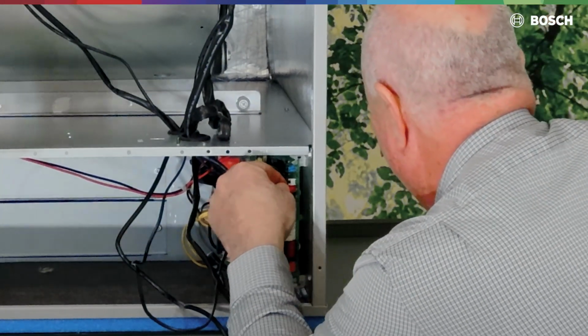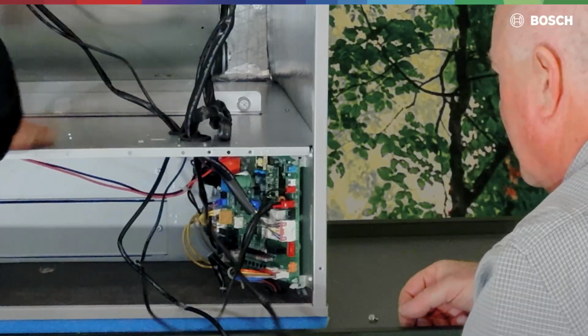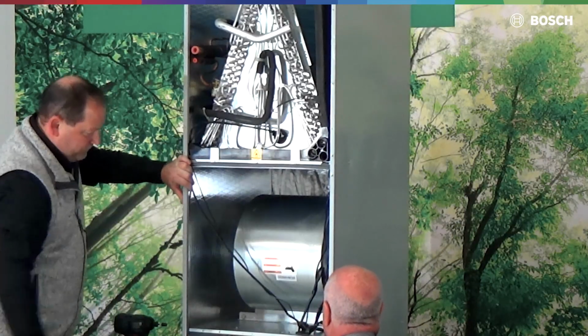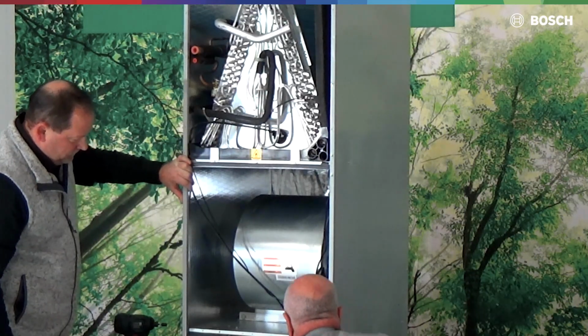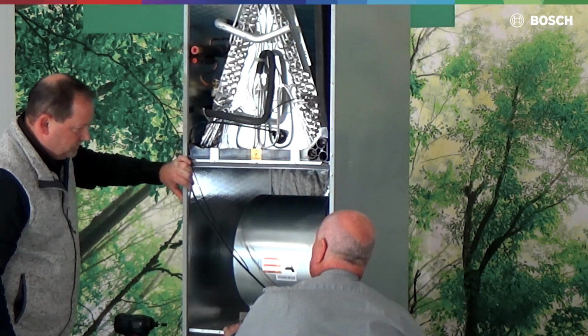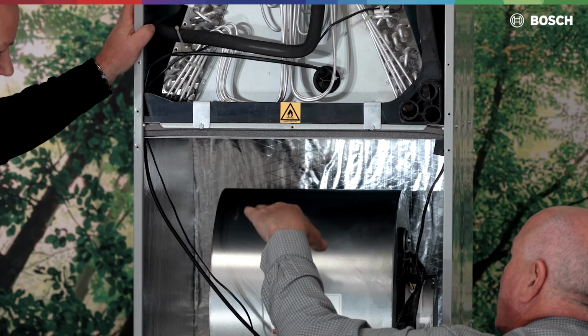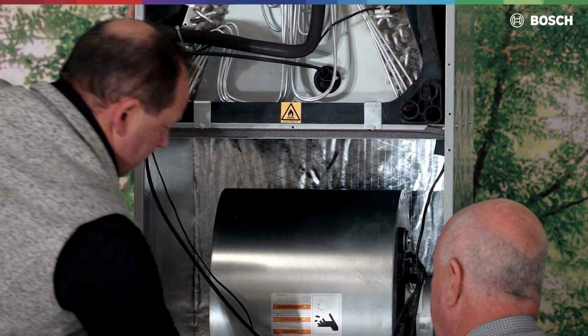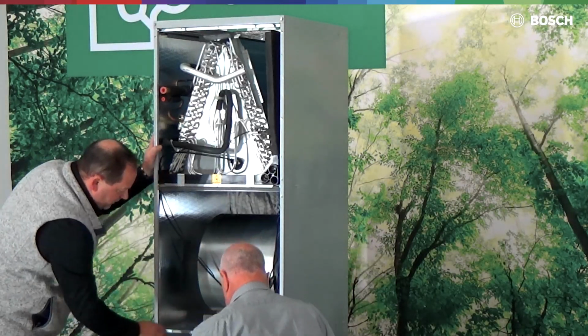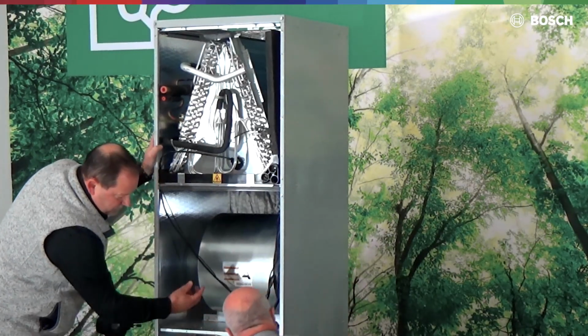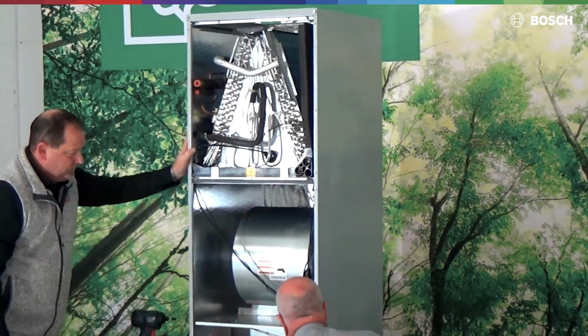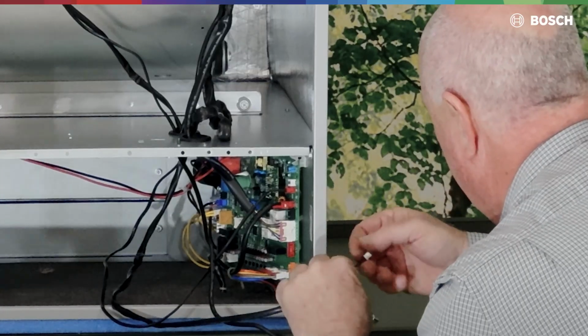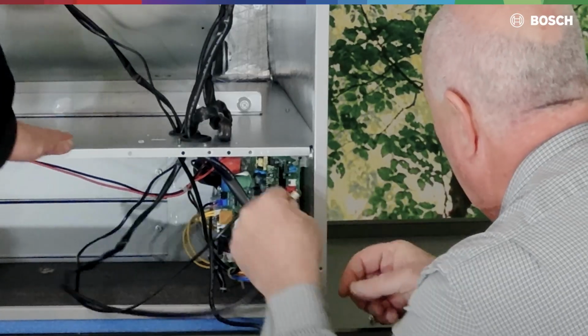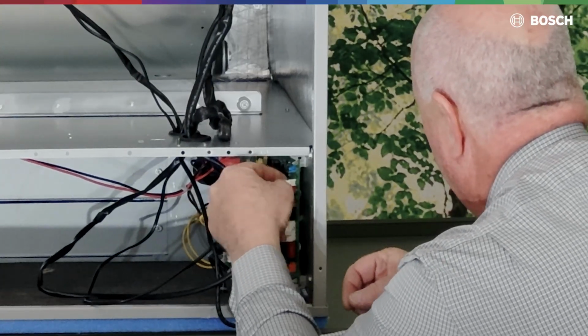Is there anything we need to do to protect this from possible water blow off? All you can do at that point would be to insulate this box to make sure you have your pan. We're going to do our condensate up here, and you could have an additional tray that may be an option in that application as well. I believe that additional tray would be installed right here. We want to make sure we don't get any water. In the event we have high static, any water or moisture below this deck possibly damage that control board.